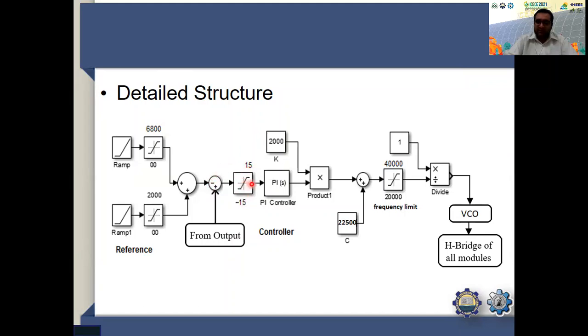That error signal will be limited by this saturator, and then passed to this PI control, and on the basis of that it is multiplied with the gain, and this bias value will be added with the free running frequency of this power supply of 22,500. At 22,500 hertz, the output voltage of these three modules will be 8.8 kilovolt. So based on the bias value this will be producing, and the sum of the free running frequency, either our frequency will be increasing or decreasing.